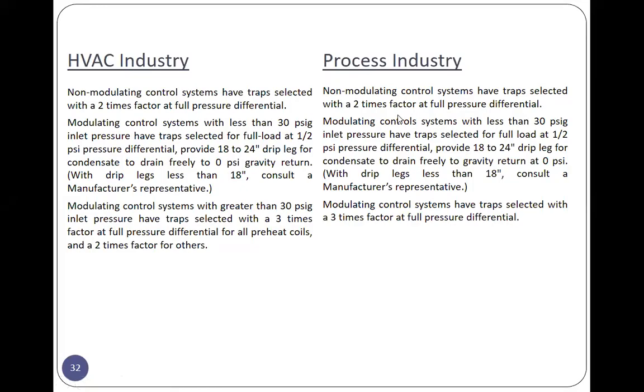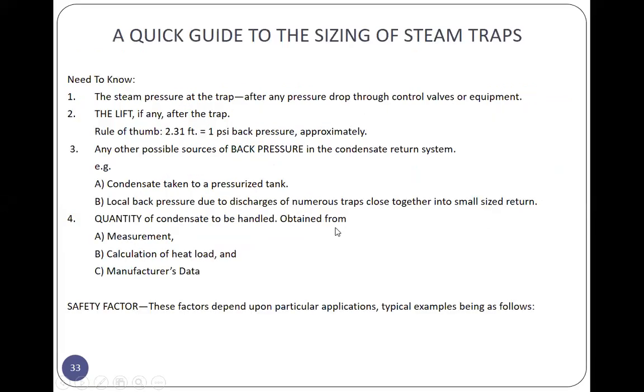For process industry, almost the same, pero lang dito sa last. Modulating control system have trap selected with a 3 times factor at full pressure differential. Ito yung quick guide to the sizing of the steam trap.